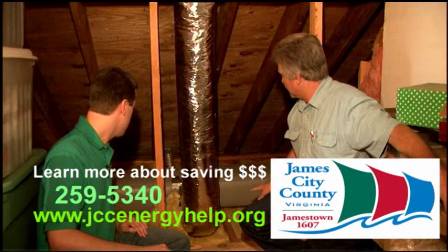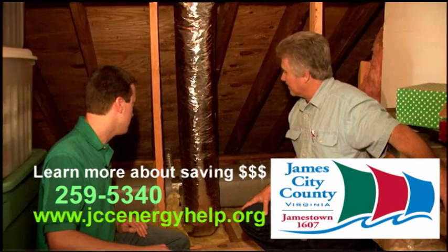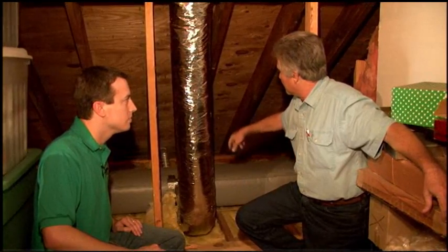Another thing is the insulation here. This particular home has an effective R value of R13 of insulation, and that's due to the gaps between the boards and the insulation, and some of it being compressed.